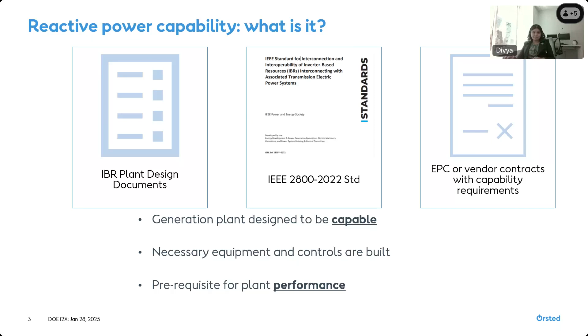It cannot be retrospectively applied. In some cases we may get lucky, but in many cases, especially today, it's very likely the plant may not be able to perform if it's not designed from the get-go. This means all the controls and equipment are built in, and this is a fundamental prerequisite for plant performance. It's part of the design decision, and if you don't decide to have this capability, it's not likely to exist, especially in large transmission connected assets.